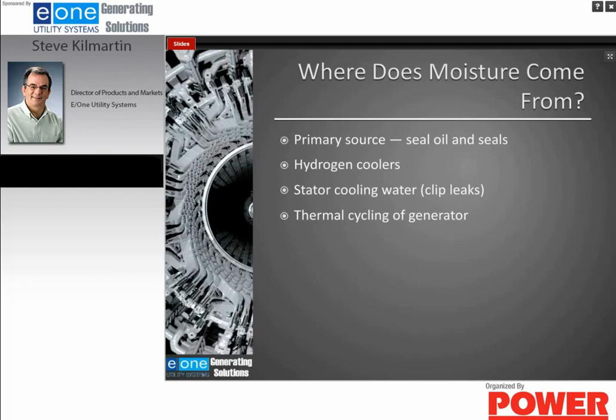As long as your seal oil treatment equipment is working properly, there's no issue. But if that breaks down, you can get moisture in your seal oil, which will result in moisture in your generator.